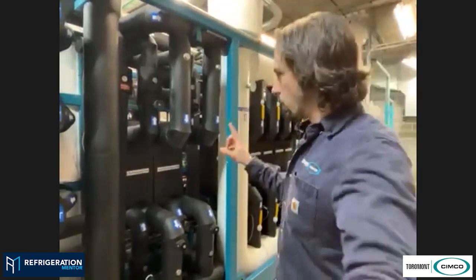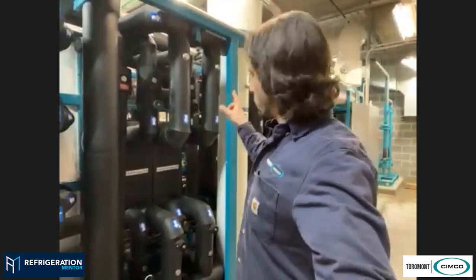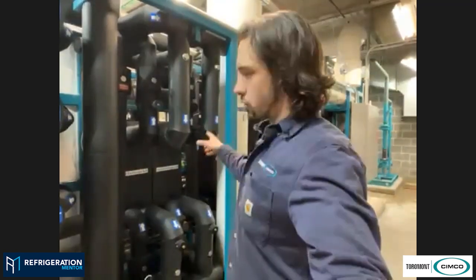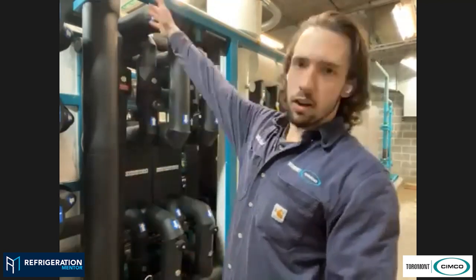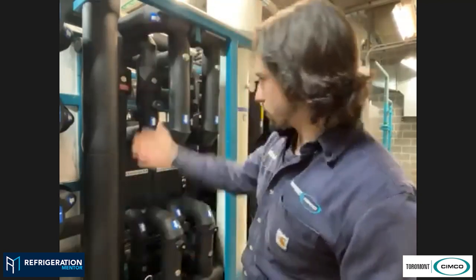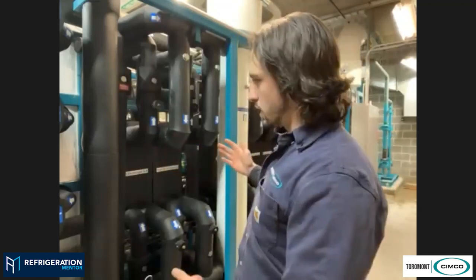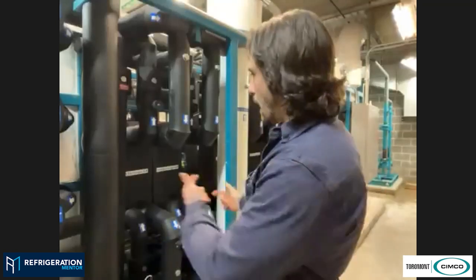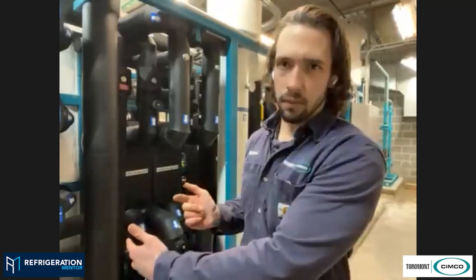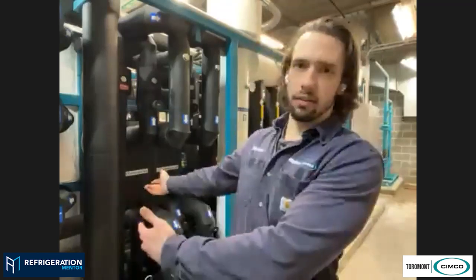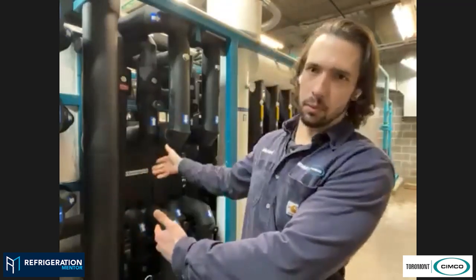With the cold suction gas returning from our DX evaporators over here, Cimco's control system is determining a target compressor superheat set point based on discharge temperature and or compression ratio. There is a motorized ball valve with a bypass line in parallel to this heat exchanger. So in the event that we need less superheat at the compressor, we can bypass that heat exchanger entirely.